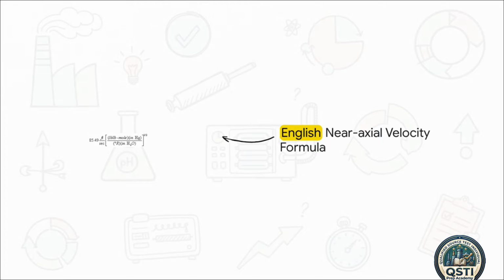Now, as this next formula writes out, you'll see the English system equivalent. The overall mathematical structure is exactly identical to the metric version, but look at the constant. It shifts to 85.49. Why the change? Because we're utilizing inches of water for pressure, degrees Rankine for temperature, and calculating our final answer in feet per second. Definitely memorize that 85.49 constant for the exam. It's going to come up for sure.